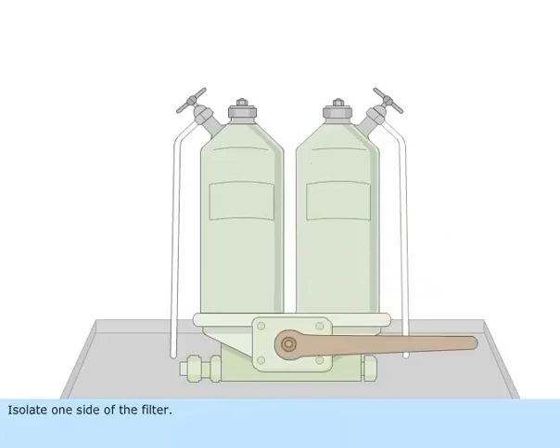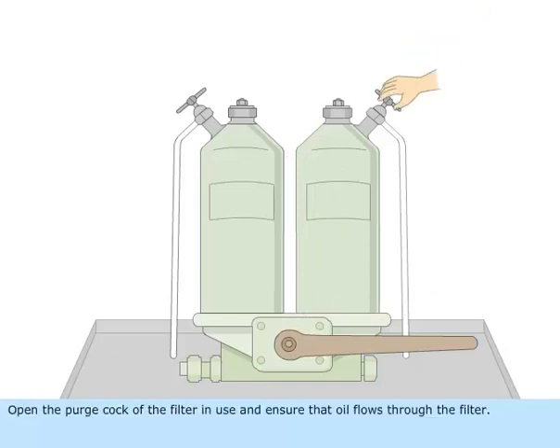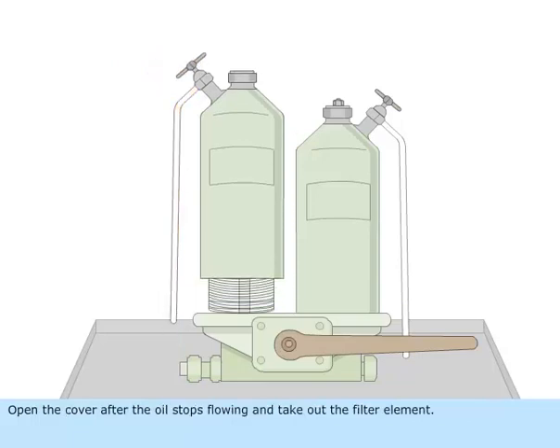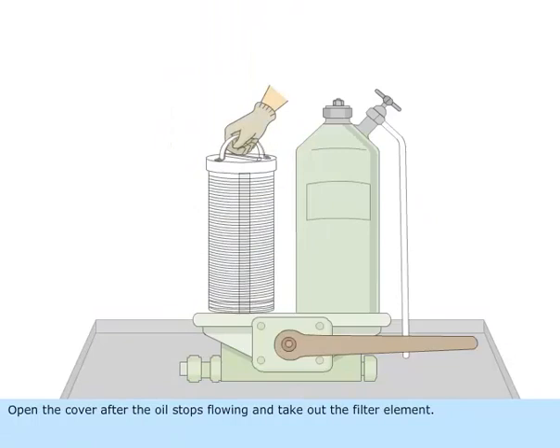Isolate one side of the filter. Open the purge cock of the filter in use and ensure that oil flows through the filter. Open the purge cock of the filter which is not in use. Open the cover after the oil stops flowing and take out the filter element.